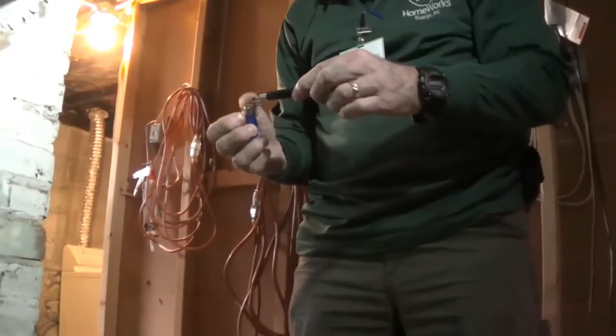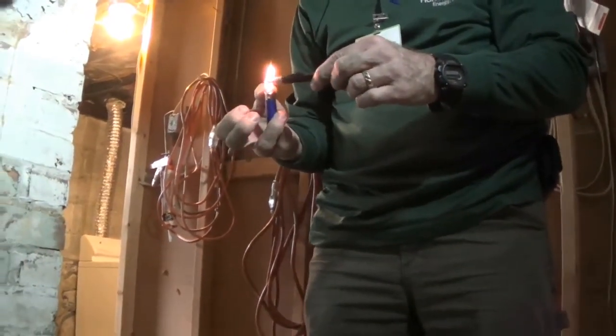We turn our heating system back on with the power switch. And we can hear some things happening. It doesn't fire up right away because it's got some safety checks to do. There we go. 1, 2, 3, 4, 5, 6, 7, 8, 9, 10, 11, 12, 13. Looking better. So the smoke is getting pulled sideways a little better. It's still not stellar, but definitely better than before.